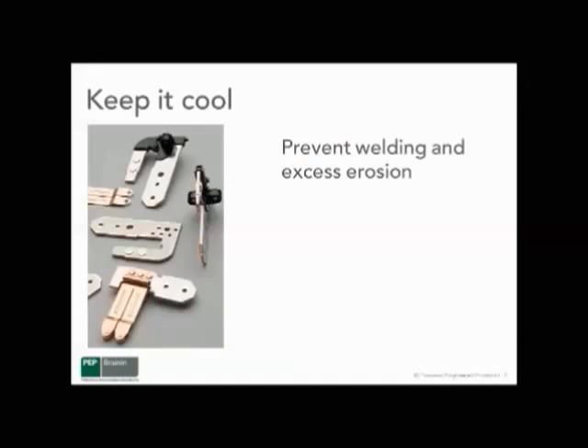Keeping the contacts cool is a very important consideration in all electrical contact systems. You do this by choosing highly conductive terminals and blades, using thicknesses of material adequate to carry the current, and doing everything possible to design a geometry which will move as much heat as possible away from the contact system. Keeping the contacts cool will minimize erosion and help to prevent welding, which can lead to catastrophic failure.